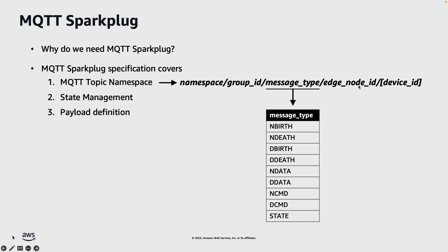Finally, the node ID represents nodes that provide a local protocol interface to devices, and the device ID represents the individual device itself, like a PLC, RTU, or a sensor. Moving on to state management, the spec provides a mechanism for communicating state using birth and death messages, which under the hood uses MQTT features like last will testament and keep alive.